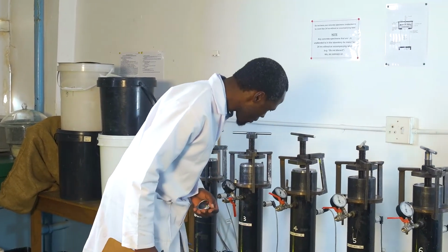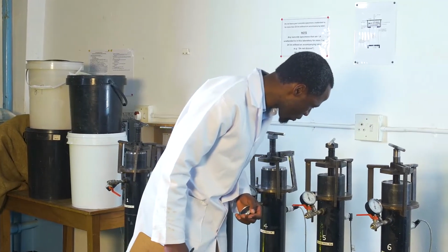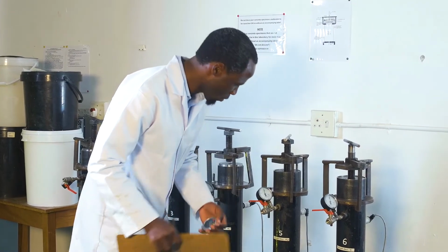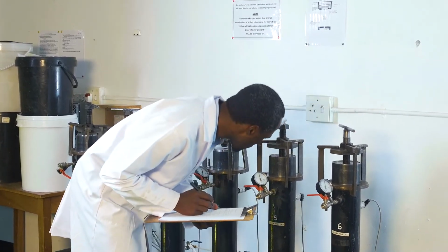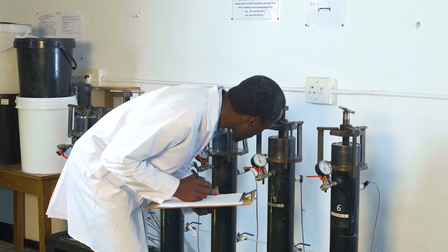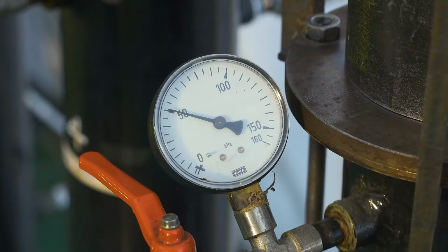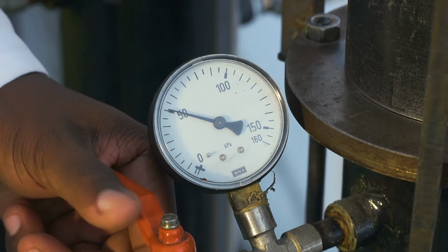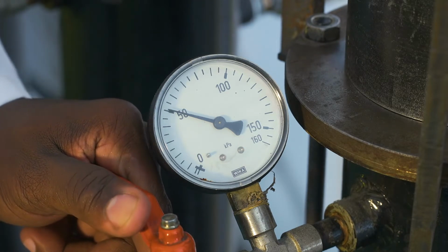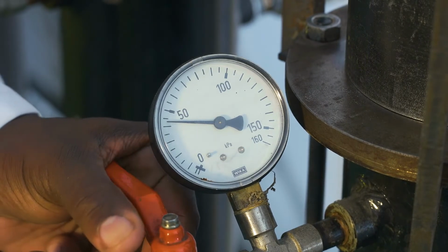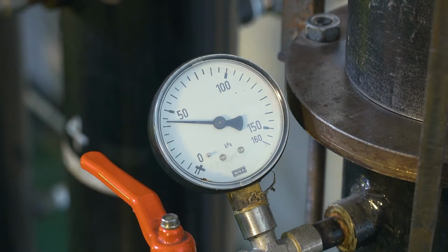The pressure drop in the gas chamber should be recorded at 15-minute intervals throughout the tests. The recording of the pressure drop in the gas chamber can be done manually, or it can be automated using a suitable data logger. The test is terminated when whichever one of 2 conditions is met. The first condition is if the pressure has dropped to about 50 kilopascals. The second condition is if at least 6 hours have lapsed since the start of the test.